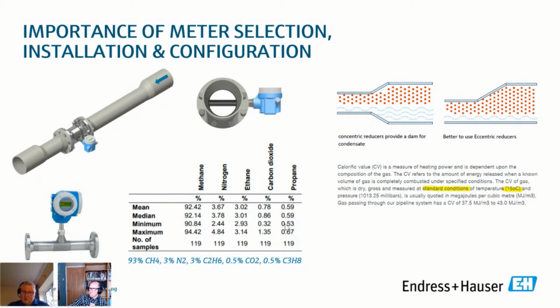And we see this a lot with people looking at efficiency calculations of boilers, and they've got gas meters that are not corrected to 15 degrees C properly. There'll be a 5% error there. And again, it's the gross CV that you're using. Typically in the National Grid, we're looking at something between 37 and 43 megajoule per cubic meter, and that averages to just under 40 megajoule per cubic meter.